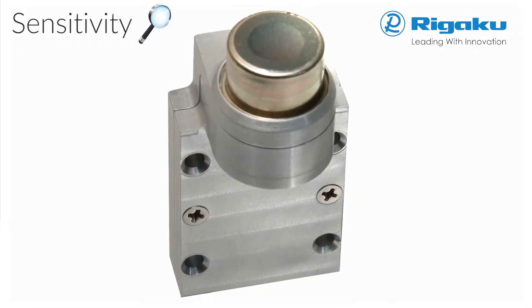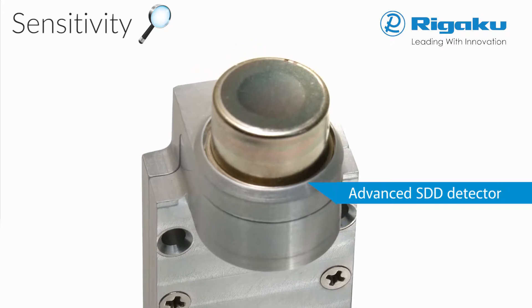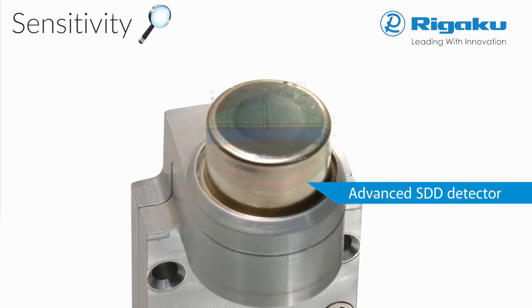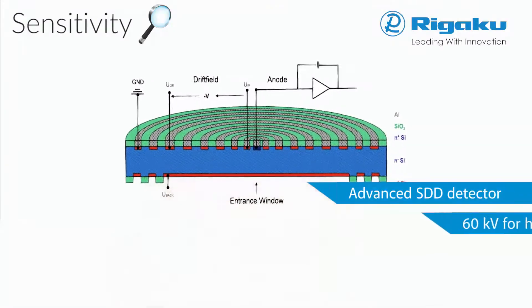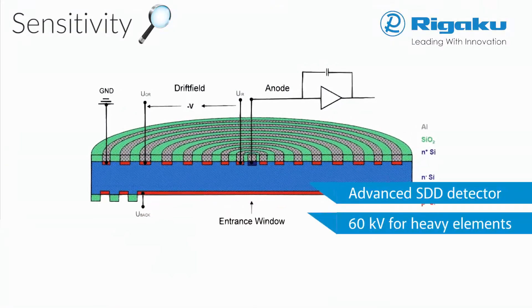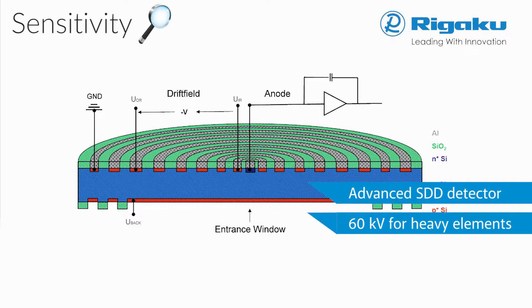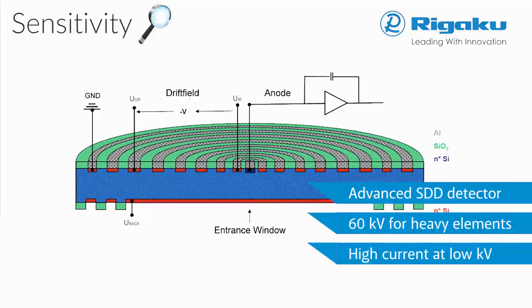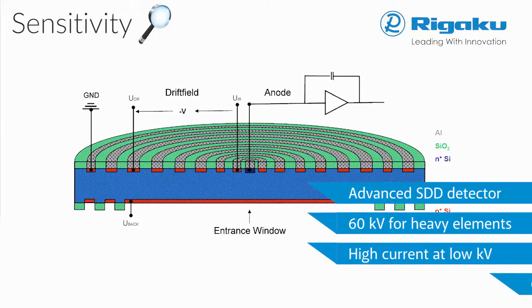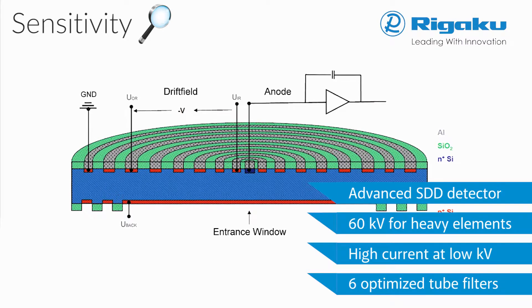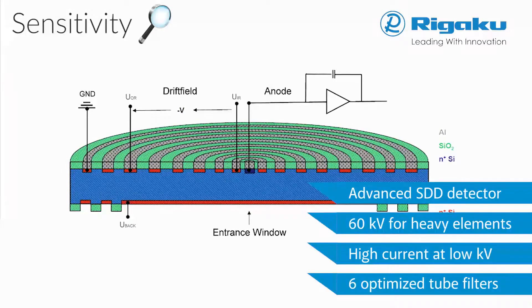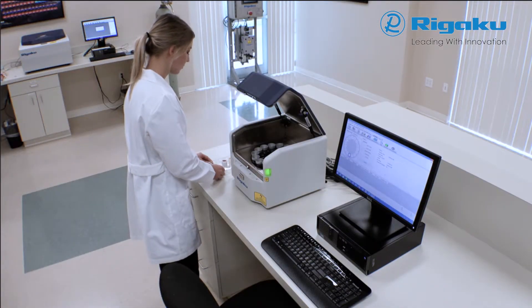Sensitivity is primarily a function of the X-ray tube and detector. 60 kV excitation with six optimized filters, together with high current at low voltage, delivers highest sensitivity across the periodic table.